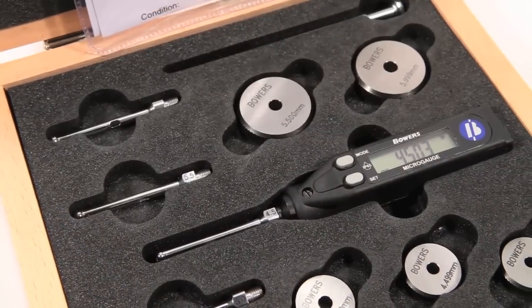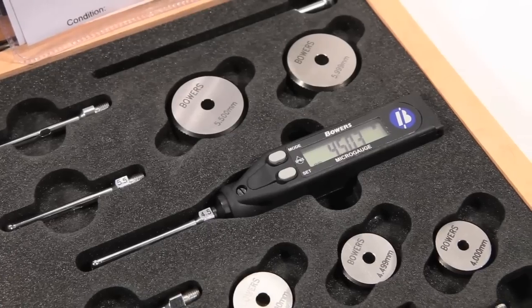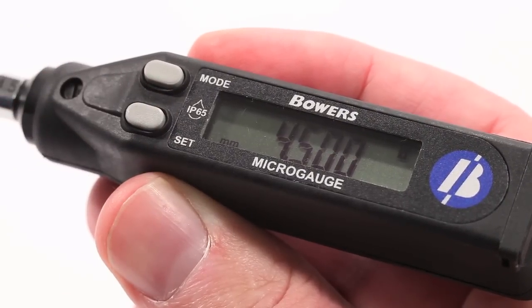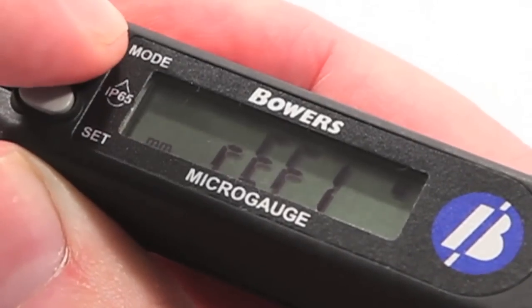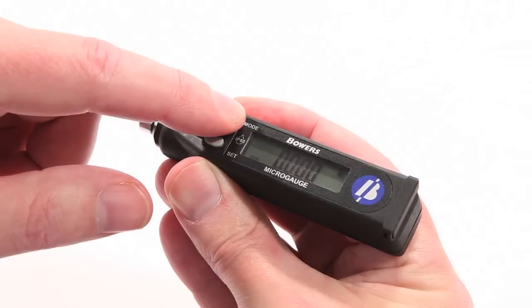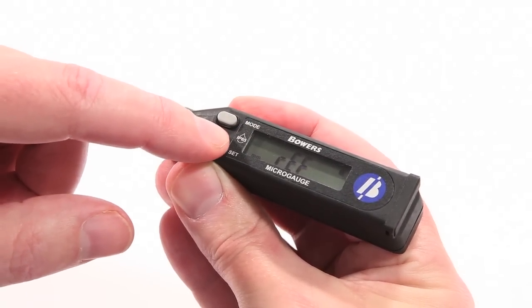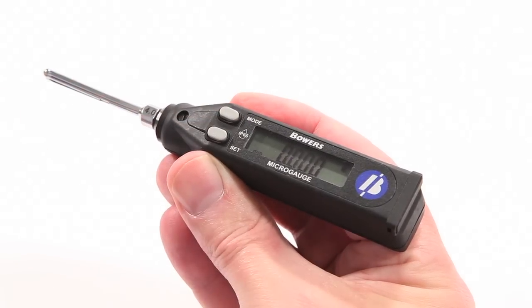All setting rings are supplied with UKAS certification as standard. To switch the micro-gauge on, simply press Set. The micro-gauge allows two independent reference values to be set, Ref1 and Ref2. By pressing Mode until Ref appears and then pressing Set, either Ref1 or Ref2 can be selected as required.